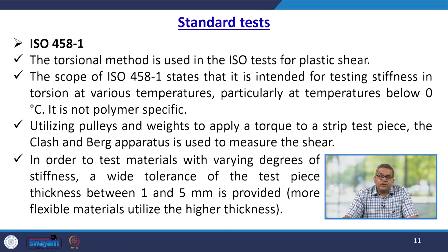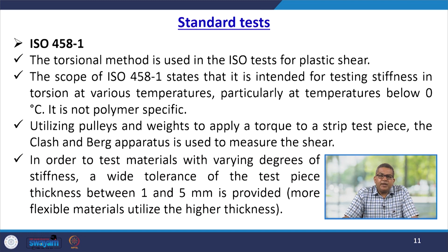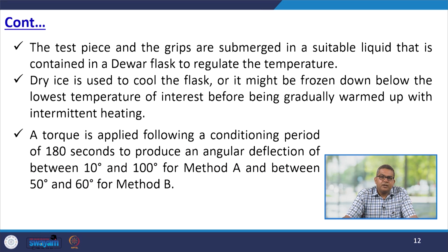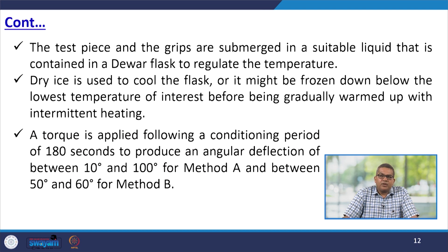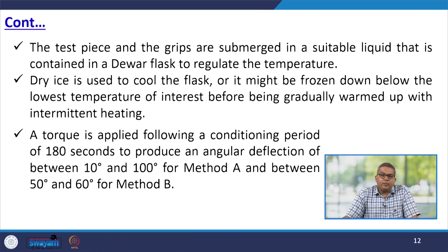Utilizing pulley and weights to apply a torque to a strip test piece, the Clash and Berg apparatus is used to measure the shear. In order to test materials with varying degrees of stiffness, a wide tolerance of test piece thickness between 1 and 5 mm is provided — more flexible materials utilize the higher thickness. The test piece and grips are submerged in a suitable liquid contained in a Dewar flask to regulate the temperature. Dry ice is used to cool the flask, or it might be frozen down below the lowest temperature of interest before being gradually warmed up with intermittent heating.